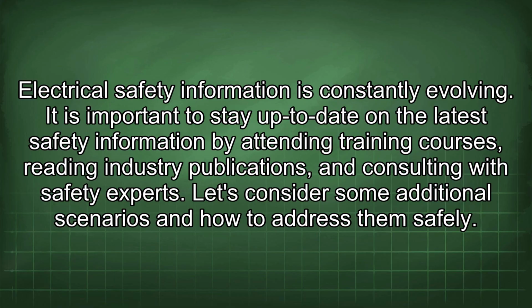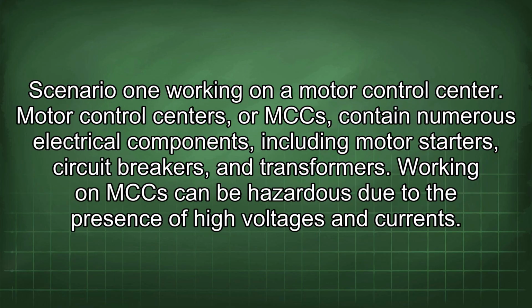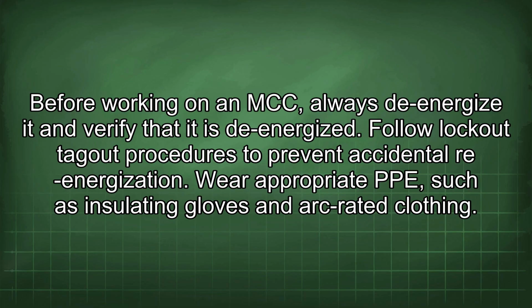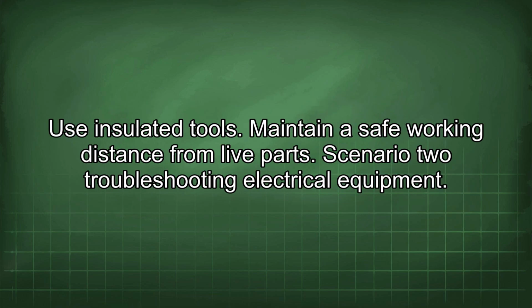Let's consider some additional scenarios and how to address them safely. Scenario 1. Working on a motor control center. Motor control centers, or MCCs, contain numerous electrical components, including motor starters, circuit breakers, and transformers. Working on an MCC can be hazardous due to the presence of high voltages and currents. Before working on an MCC, always de-energize it and verify that it is de-energized. Follow lockout-tagout procedures to prevent accidental re-energization. Wear appropriate PPE such as insulating gloves and arc-rated clothing. Use insulated tools. Maintain a safe working distance from live parts.